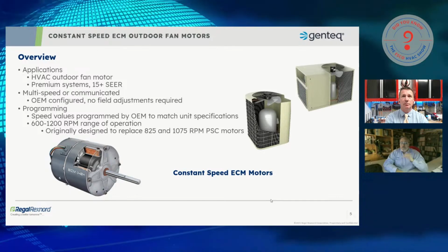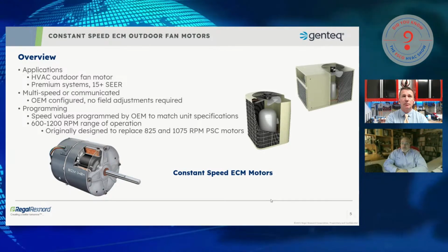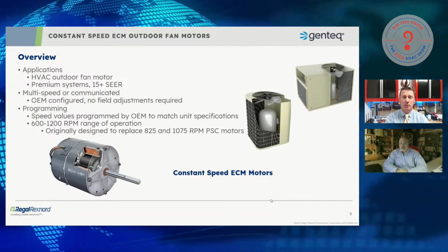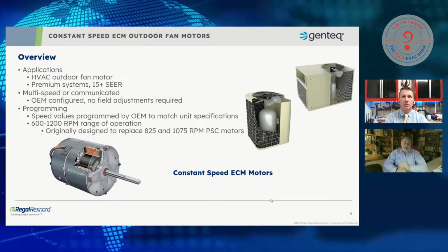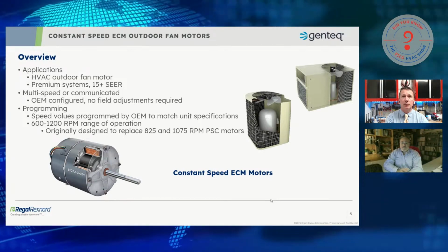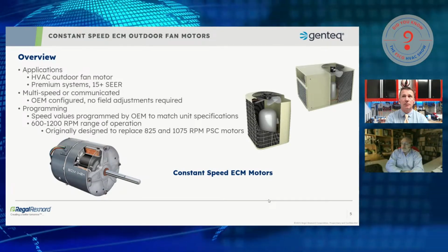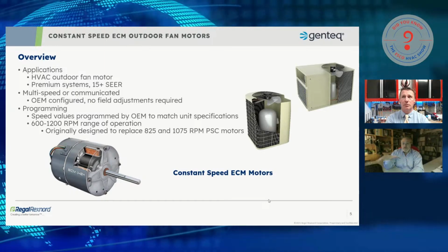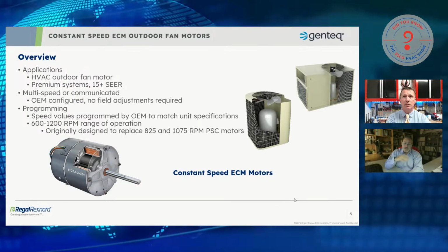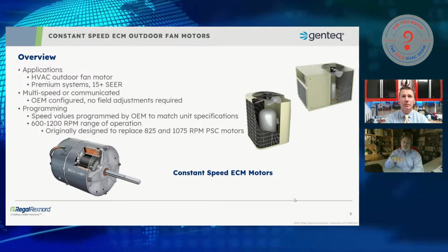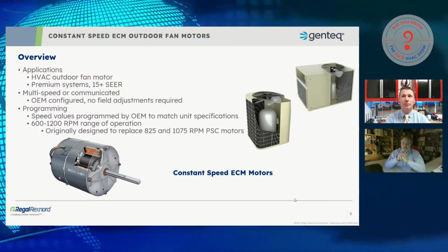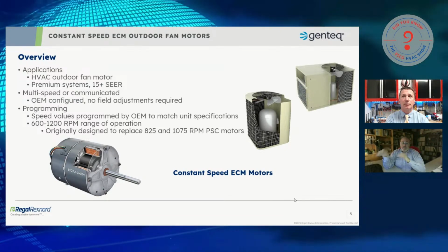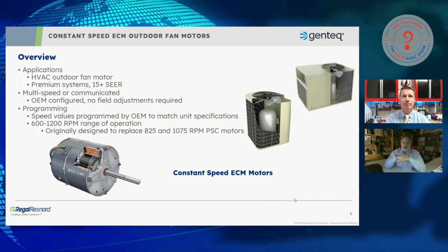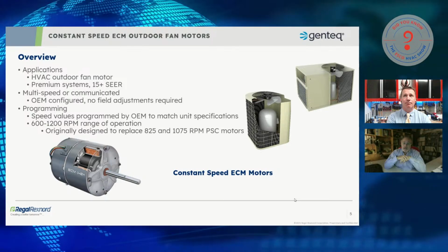Just because there may have been an 8-pole PSC in that equipment previously doesn't mean they're going to use strictly 825 or strictly 1075 if it was a 6-pole. And we'll talk a little bit more about this as we go through the presentation as well, because it's very important to understand that these constant airflow motors do not have fixed 1075 or 825 RPM operating points like the PSC motors that they replaced.